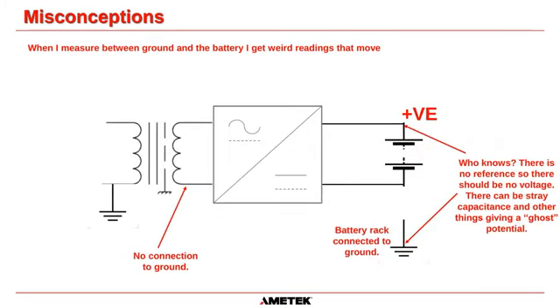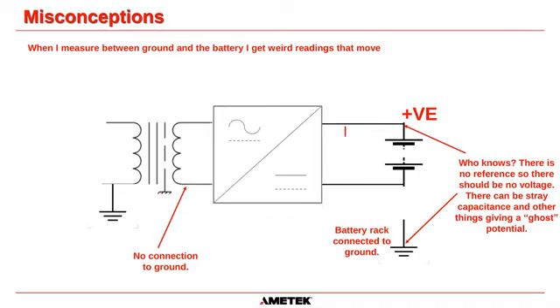Sorry. The next misconception is when I measure between ground and the battery, I get weird readings and they move. Okay. Well, remember, if we go back to the start, if we have a true isolation transformer and we have a charger that does not have any kind of ground detection system on it, then we don't know what the voltage between positive and ground and negative and ground is. And when you put your Fluke between positive and ground and negative and ground, yes, your Fluke is a high resistance piece of equipment, but it does have resistance. So it is going to tend to pull that down to 0 volts. So let's say you measure it at 35 volts to start off with, there's some kind of stray voltage in there. It will start to tend down towards 0 volts. That's not an issue as long as the system doesn't have ground fault detection in it.